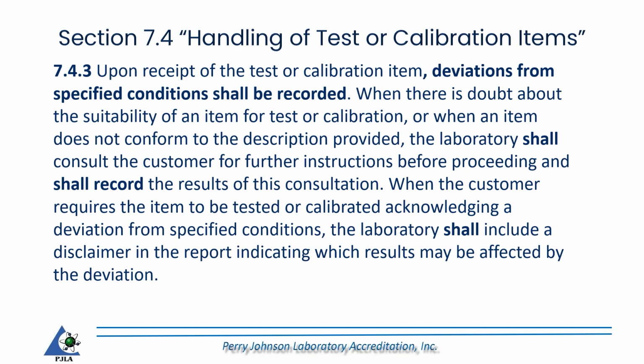Moving on to the next clause, we'll look at this. It's kind of a long clause here. We'll dissect it a little bit. So go ahead and read it. We have a few shalls in here. Upon receipt of the test or calibration items, deviations from specified conditions shall be recorded. When there is doubt about the suitability of an item for test or calibration, or when an item does not conform to the description provided, the laboratory shall consult the customer for further instructions before proceeding and shall record the results of this consultation. I have three shalls right there.